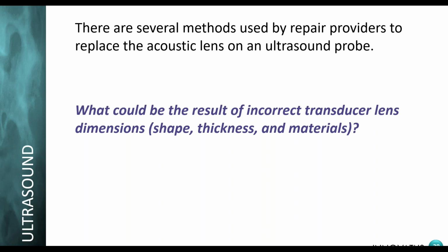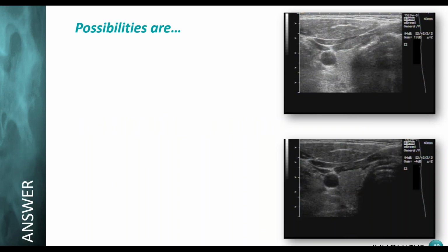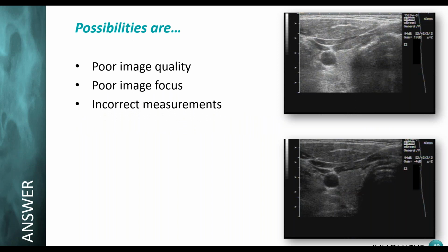The lens does all kinds of different things. The reason it's called a lens is because it is a lens. These here are optical lenses. The lens on a transducer is an acoustic lens, so it focuses the acoustic energy. If you don't have the proper shape, you're not going to focus the beam properly, and you're going to have poor image quality. Poor image quality, poor focus, incorrect measurements. You're looking at these images here. By the way, this is my thyroid. So this area right here and this area right here.